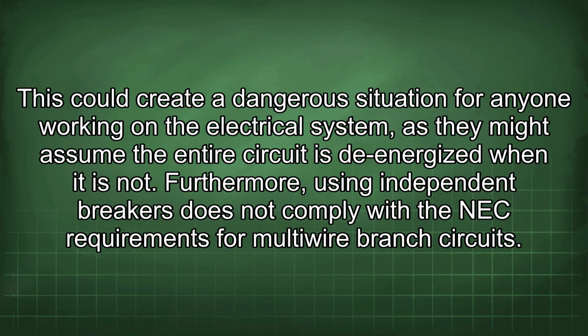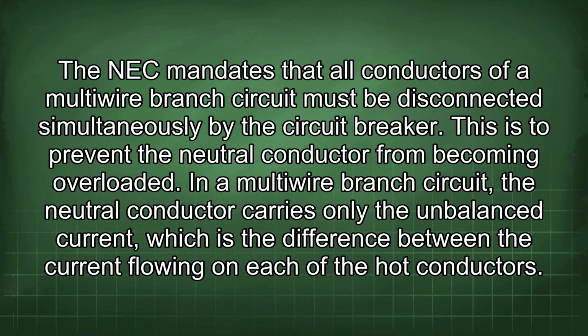Furthermore, using independent breakers does not comply with the NEC requirements for multi-wire branch circuits. The NEC mandates that all conductors of a multi-wire branch circuit must be disconnected simultaneously by the circuit breaker. This is to prevent the neutral conductor from becoming overloaded. In a multi-wire branch circuit, the neutral conductor carries only the unbalanced current, which is the difference between the current flowing on each of the hot conductors.